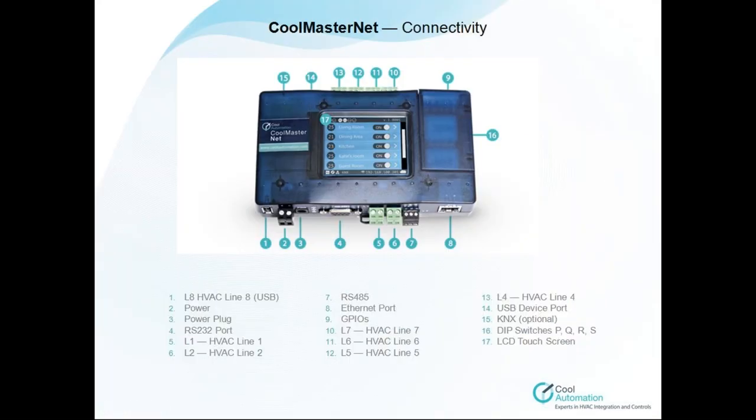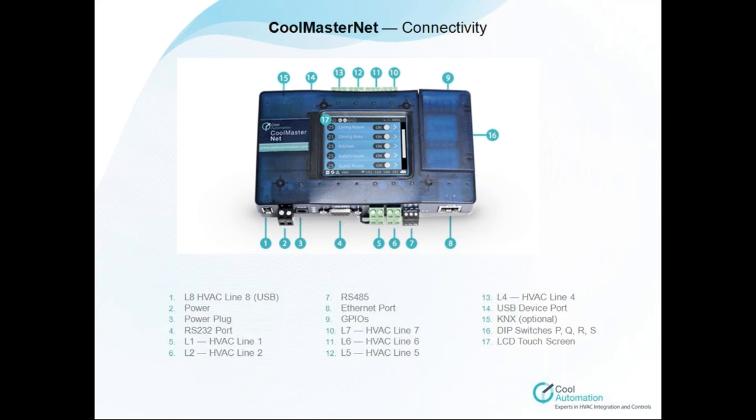Let's make a short conclusion, what we have until now. The first point is L8, the connector, USB connector responsible for Fujitsu devices. Fujitsu devices are connected via external adapter, via long adapter, and supplied by Fujitsu. Number two and number three are the power jacks responsible for the external power. It's very important to mention that our device is a DC powered device, powered by 9 to 24 volts DC.